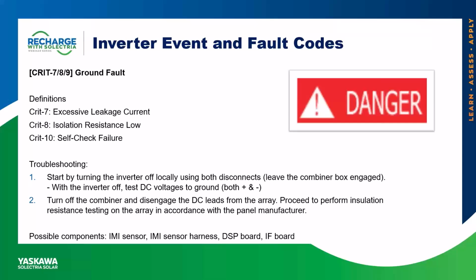Next would be CRIT 8, insulation resistance low. This code specifically implies a low insulation resistance value is being detected on either the positive, negative, or both DC conductors. This is a true ground fault or array side issue. Lastly, here is CRIT 10, self-check failure. This code implies something in the ground fault's detection circuit has failed. Again, we always want to verify nothing external to the inverter has caused this.